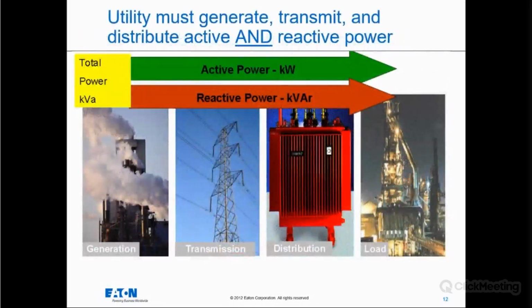Certainly, utilities want to use their grid in the most efficient fashion. So they would rather minimize the amount of kVAR that they're pulling through their system and maximize the amount of kW so that they use their electrical grid as efficiently as possible. But uncorrected and left the way it is, what do you want to do here? You're looking at kW, kVAR being pulled through the system.